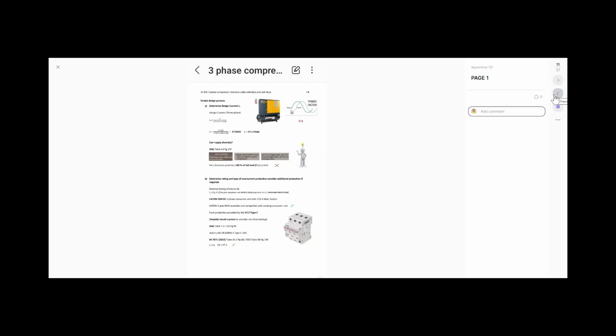Okay. So we've got our design current IB. Then we can consider determining the rating and the type of overcurrent device, and whether we need to consider additional protection. Well, the cable's going to be a wire armour cable, running in ducting, so there is no requirement for additional protection. So I've only got to think about overcurrent protection.